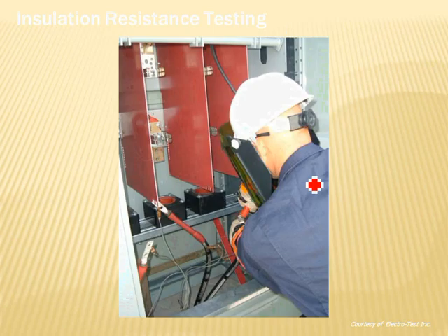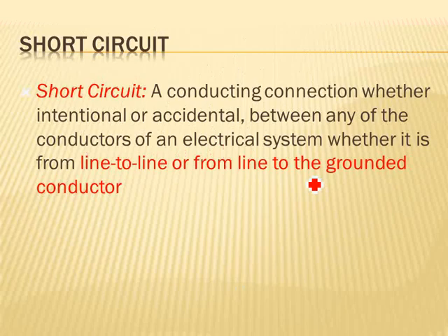Let's go into insulation testing, short circuit. I'm jumping here because of the time. I have 12 minutes exactly. Line to line or line to ground. They define a short circuit as an intentional or accidental connection, line-to-line or line-to-ground. That's a short circuit. Line to grounded conductor: if you have a phase to the grounded conductor, the neutral, that will be a short circuit.